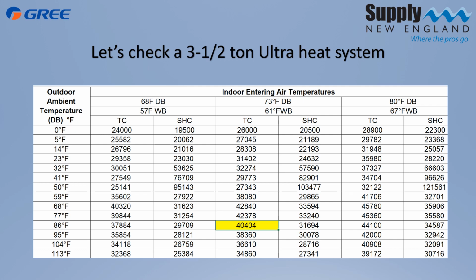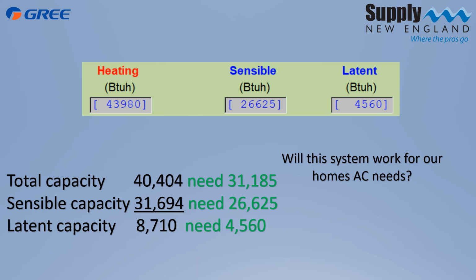Cooling load, 40,404. That's what it can give us. So let's see if it works for our environment. So it can give us 40,404. We only need 31,185. We're good. It can give us 31,694 sensible. We only need 26,625. We're good. Latent capacity, 8,710. We only need 4,560. So does this work for our system?